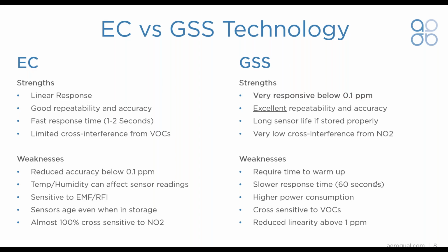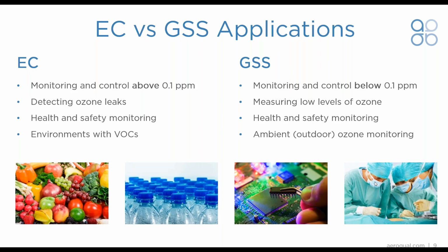So I guess the question you're probably asking is, which sensor do I use? That's going to depend on your application. If your health and safety requirements require measurement and reliability above 0.1 ppm, then the EC sensor is going to be a good choice for you. The speed of response and wide range of measurement for the EC sensor makes it a sensible option if you're looking at leak detection as well. If your applications contain VOC sources, which are volatile organic compounds, then the EC is also a good choice. For ozone sterilization applications, where levels of ozone are typically much higher, around 10 ppm being quite common, the EC sensor is ideally suited for you.